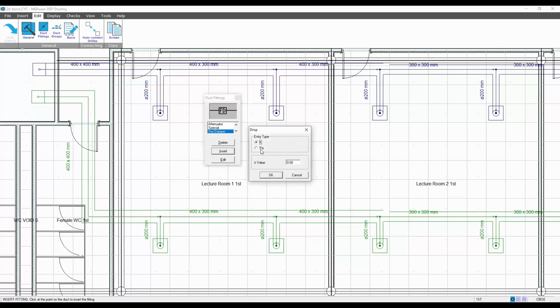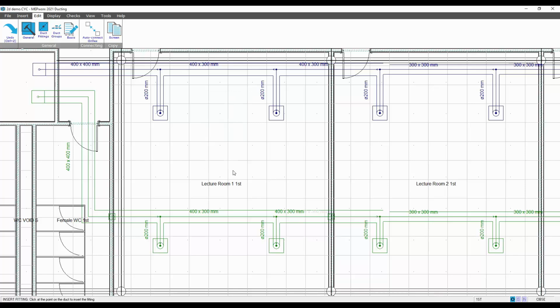I can then use the standard K value which I can apply, or I can put a resistance. And then I repeat the process with each separate partition. If I want to put a volume control damper in, first of all we would want to know the pressure at the appropriate section so we can balance the system.